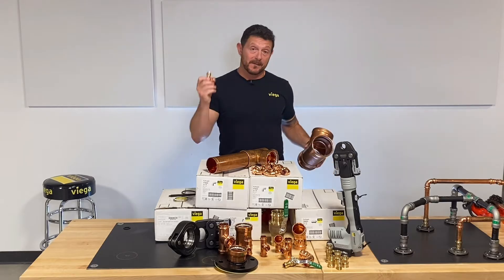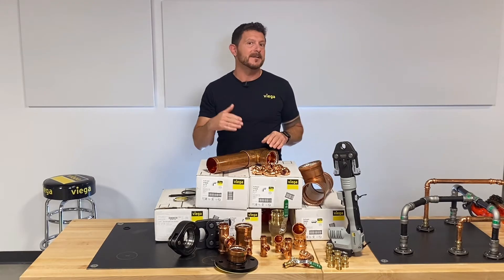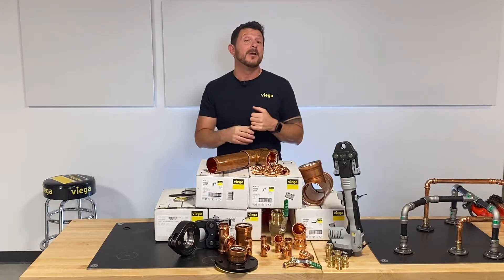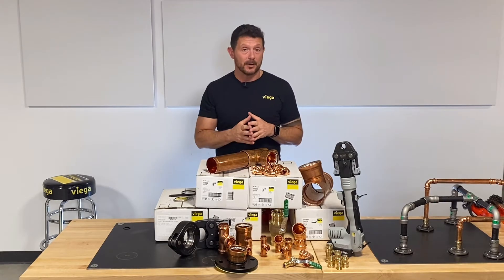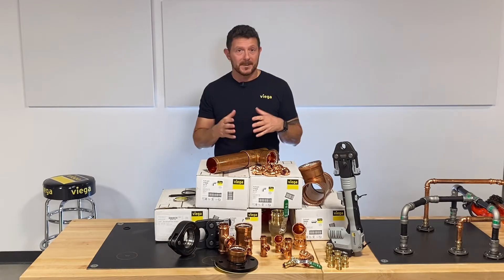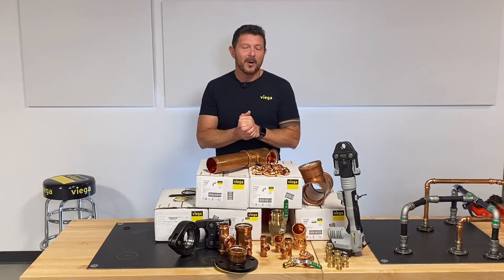Viega ProPress fittings are available in sizes half inch through four inch for hard-drawn type K, type L, and type M copper. You can also use it on soft-drawn copper in sizes half inch through inch and a quarter. Your copper just has to conform to ASTM B88 or B75 standards and you're good to go.